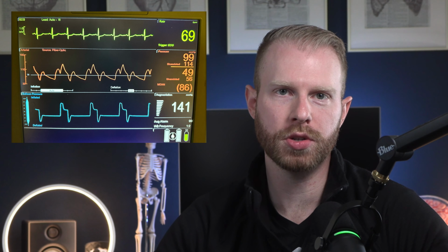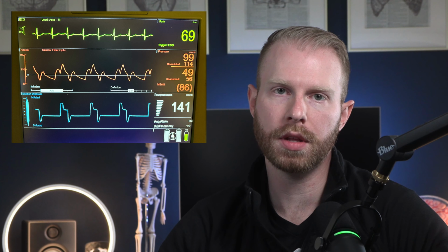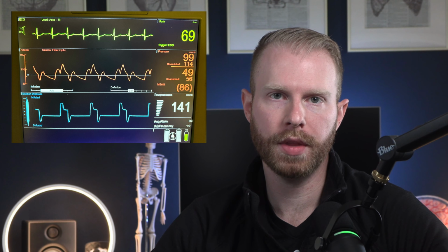And that might make somebody, if they're unfamiliar with balloon pumps, immediately think the assisted ones are lower. The systemic pressure looks lower than it does when it's unassisted. Like the unassisted, the systolic and diastolic are higher. But the whole point of the assistance is to take workload off of the heart. And then you get this diastolic augmentation that you guys talk about. And that's the number that's built in, which is that 86 down there. So I don't know exactly what formula they use. But again, if you were to average out unassisted and assisted solely, it'd be like 70. But because of that big diastolic augmentation peak that goes in there, that gives you the actual MAP of 86.